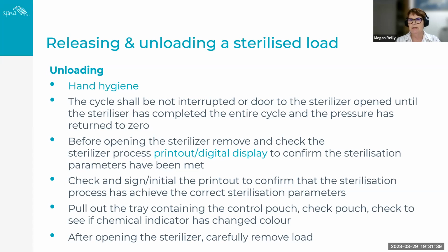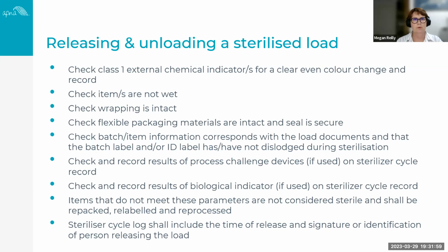So different indicators have different color changes. So again, you need to look at the manufacturer's instructions to determine what is the initial color and what is the expected color change following the sterilization. Always open the sterilizer carefully and carefully remove the load. Again, we don't want to compromise that sterility process. So when we release the load, we're checking the class 1 external chemical indicator for a clear, even color change. And ideally, you should record that result. Check that the packs or the items are not wet if they're critical, that the wrapping, the packaging is intact, that if it's flexible packaging like the self-seal pouches, that again, the seal is intact and it's secure.